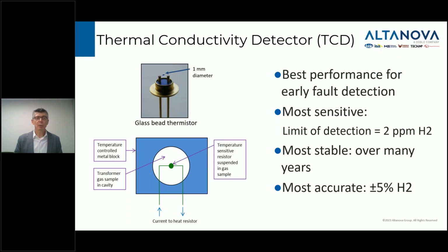And they're also extremely stable over many, many years. So that means that a very small change in hydrogen concentration, even if it's years down the road, these systems are really good at picking that up. They're also the most accurate. Oftentimes they benchmark very well against the DGA lab. A little bit of how the technology works here is very simple. There's a small glass bead thermistor. A thermistor is a temperature variable resistor, as you may know. So we have this tiny bead, less than 1 millimeter in diameter, suspended on some fine wires in a cavity filled with the gas that we've extracted from the transformer. And we pass a small current through this thermistor to heat it up.